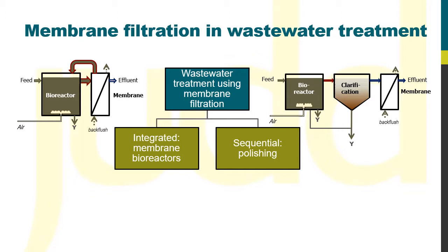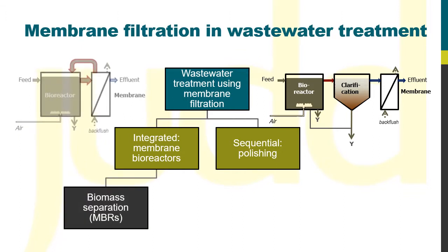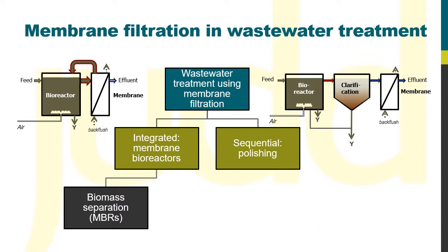In the non-integrated case, the membrane is normally referred to as a polishing process. Within the integrated processes, we have the conventional activated sludge process where the membrane retains the biology in the tank, filters the water down to well below 0.1 micron, and as a result produces a largely clarified and disinfected water.